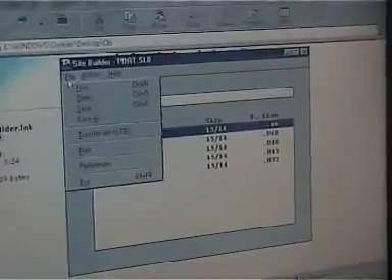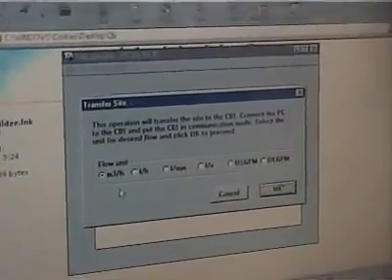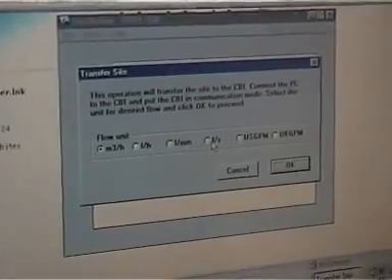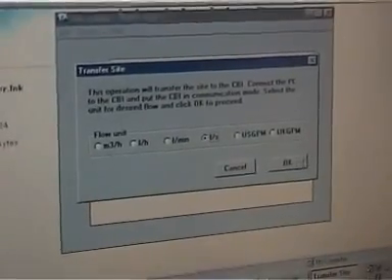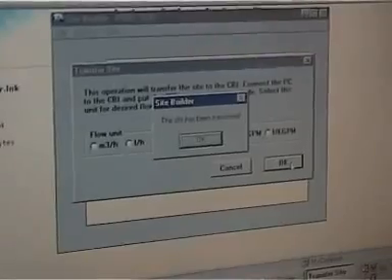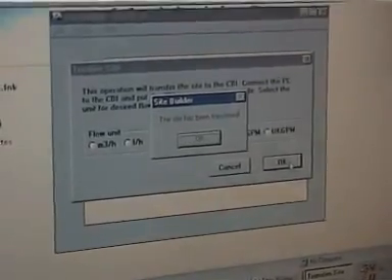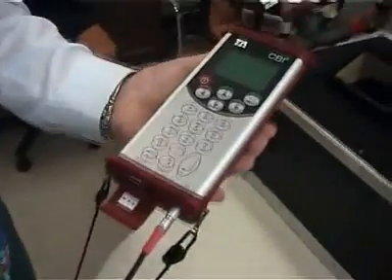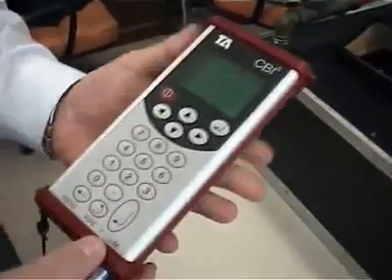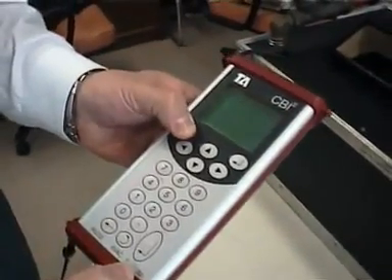To transfer the information from your PC to your CBI, you open up file, come down to transfer to CBI, choose it. It asks you the flow rate that you want it in. You can choose your flow rate at this stage. Liters per second. Hit the button OK. It comes up and tells us that our site has been successfully transferred. Remove the communication port from the PC. Ready to go to site now. Turn the machine off, and move to site.